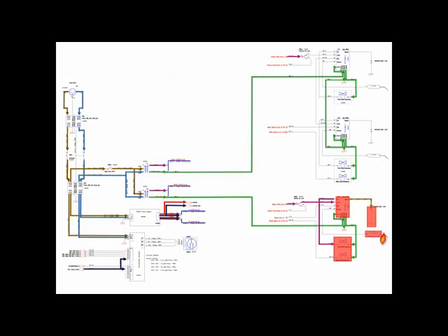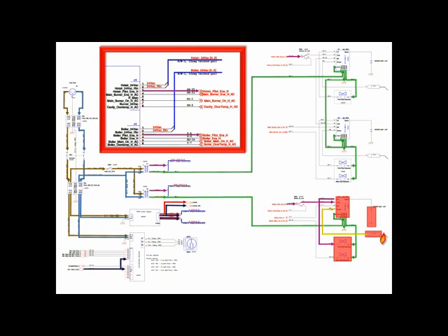The microamp sense signal is shown now on the diagram as it reaches the module, stopping the spark. And at the same time, the sense signal enables the MV output, which is sent to the relay board.